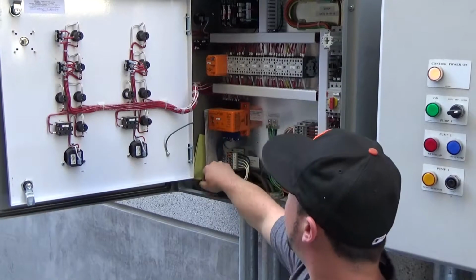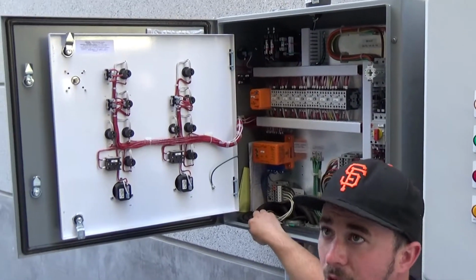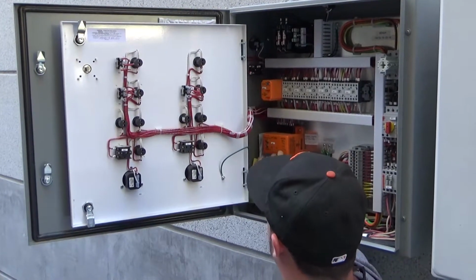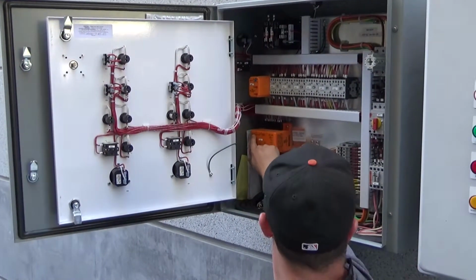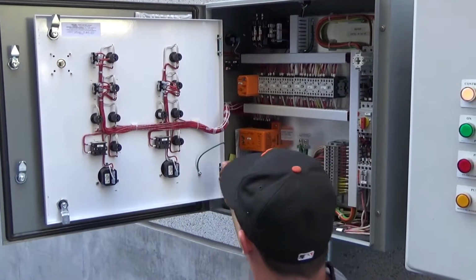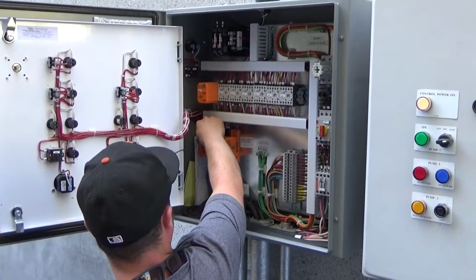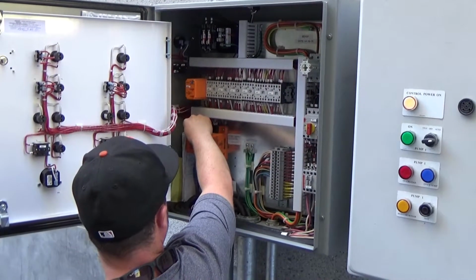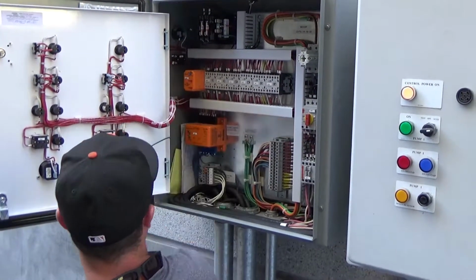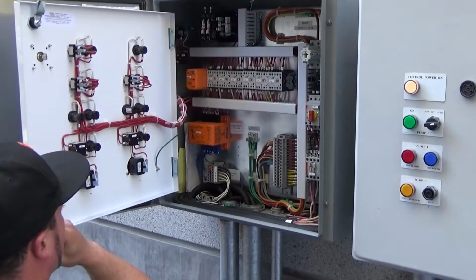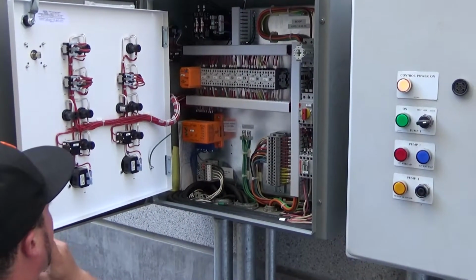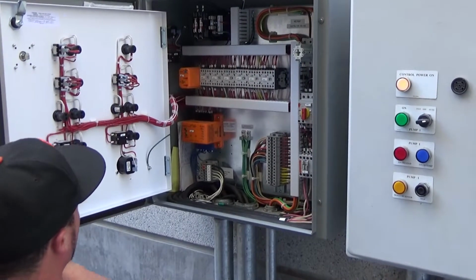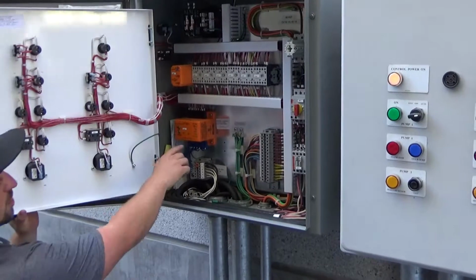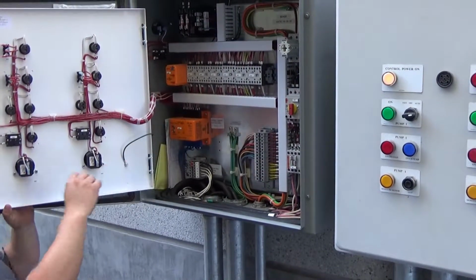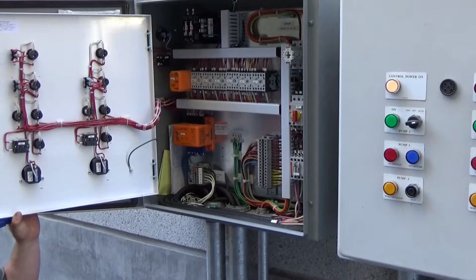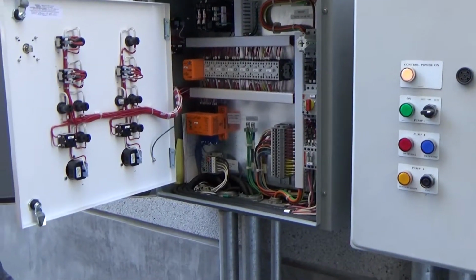This one, so if you hit high water float, this one will trip also, and that will be your clear. Okay. Actually, that resets the post too. That's a test running that pump, it sounds like. That is test running that pump. Actually, it's testing lead lag, because I saw motor 1 run, then motor 2 run. That's correct, yeah, you are correct. So if you ever have to do that, I know that if you do trip your high water sometimes, you do have to reset it here also. Does that say test and clear? Test and clear. Okay. So it's also a clear and alarm. Correct. Perfect.